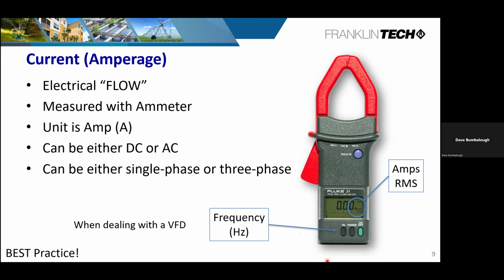Is it at full speed? Because most of the amperages that are listed on the nameplate are at max speed, at its nominal speed. So going forward, if you've got a clamp-on amp meter, I would suggest that you have the ability to measure frequency, because frequency is directly related to what your amp draw is. So the slower this product is spinning, the lower the amp draw. And there is no manufacturer, even ourselves, that has any kind of cheater sheets that show what that amperage is at a lower frequency. We just know that it's lower, right?